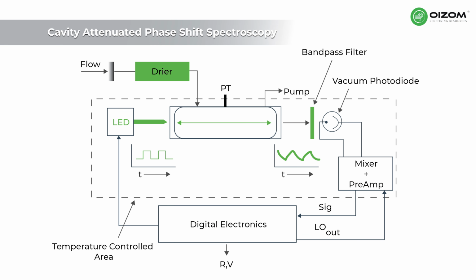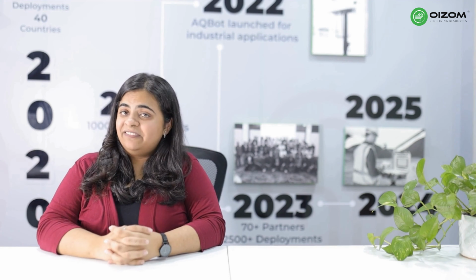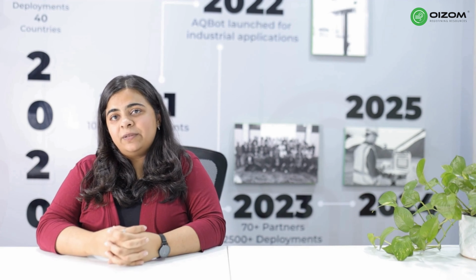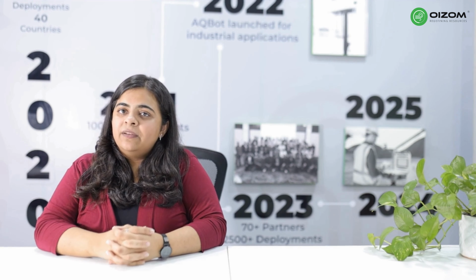2. Cavity attenuated phase shift spectroscopy, CAPS, directly measures NO2 using UV light. When NO2 is present, it changes the light's phase shift in a special optical chamber, allowing precise measurement.